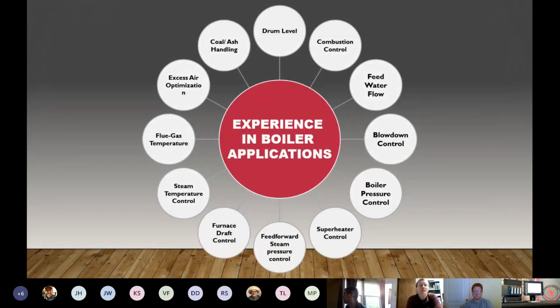Let's talk about one particular application where the HC900 really shines. This is boiler control. So when you look at a boiler, you have a lot of different control loops in there that the HC900 can accommodate very well. You have drum level, you might have combustion control. In that combustion control, you might have fuel-air ratio, which the HC900 does very well at. Feed water control, blowdown control, pressure control. You can go around this circle and pick out a lot of the different parts of the boiler, depending on the size of the boiler, where the HC900 can really shine with a single I/O rack, with a single display, and really take care of a lot of those applications.